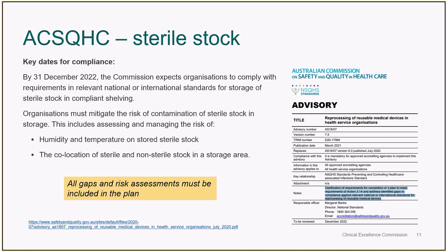You can do that by assessing and managing the risk. You need to have humidity and temperature monitoring on stored sterile stock. We're talking about stored sterile stock for reusable medical devices only. So that's where you need humidity and temperature monitoring: on reusable medical devices, not consumables. That's in the standard. Now, in a lot of sterile stock rooms, particularly in operating theatres, they co-locate sterile reusable medical devices and consumables or non-sterile stock in a storage area.